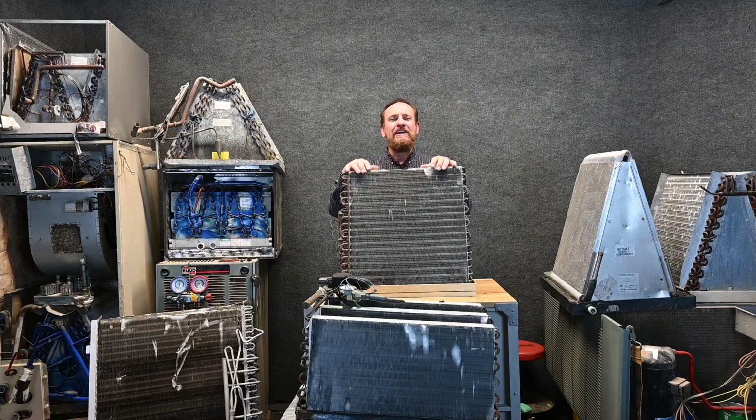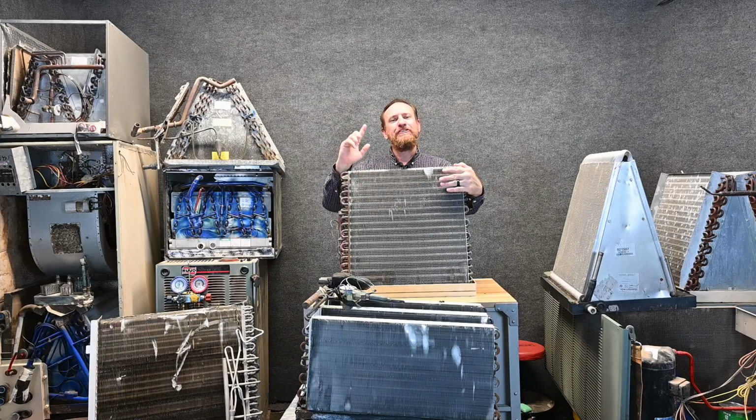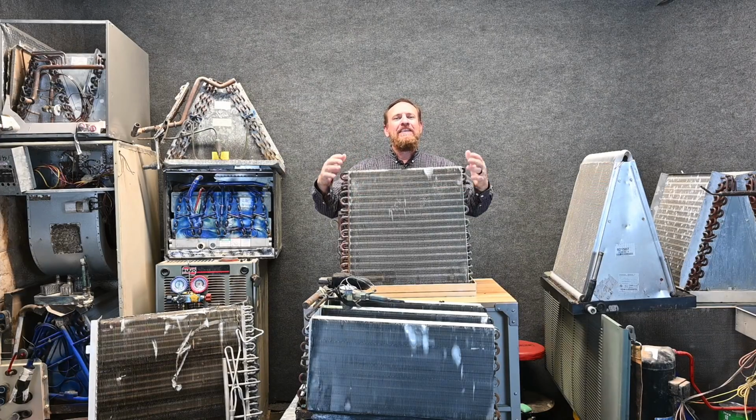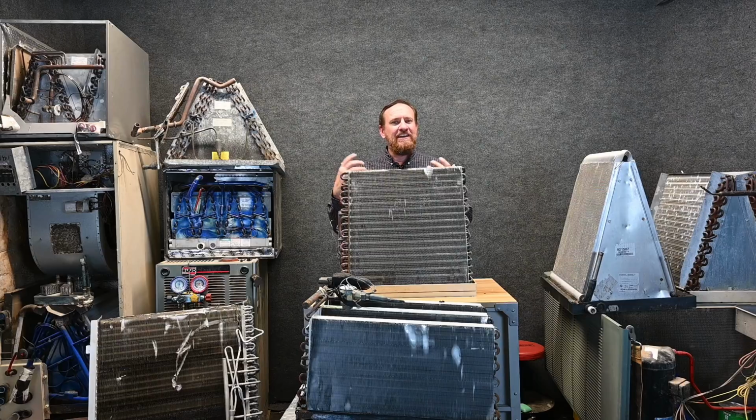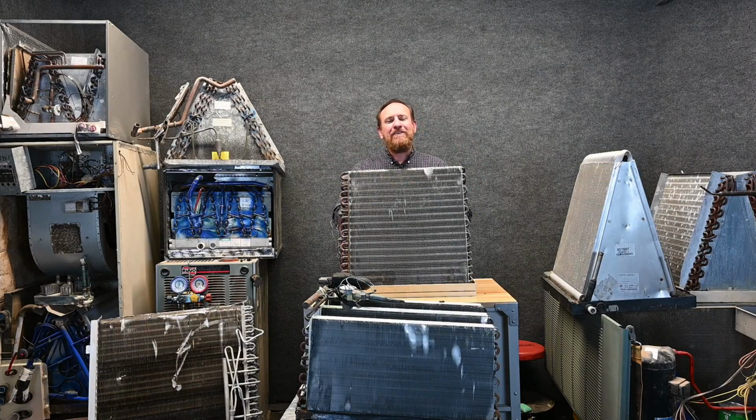Depending on what climate you're in, we're really going to need to focus on latent heat removal. So we're sensibly cooling the air, but we're also latent cooling the air. The air is going to have moisture in it. It's going to have H2O. We typically measure this with humidity, although there's better ways such as dew point. But that moisture in the air, we need to take that moisture out of the air. If we take that moisture out of the air, we dehumidify the air.